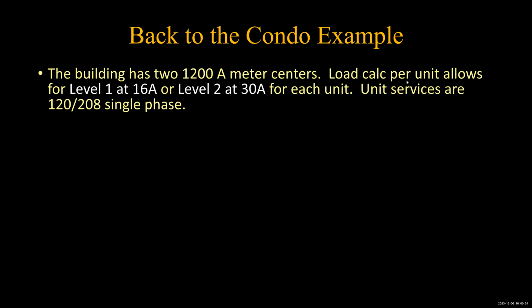You would have to show the individual units designed the way we did earlier, and then you'd apply that 23% diversity factor. I mean, that's legit, because you're including the EVs as 125% for each unit. And so you could do that, but it's probably going to bump up your individual unit service significantly. I'd love to see what the number result comes out. I'll try that sometime. So I would say try it both ways, run the calculations both ways, and then ask the owners what they would prefer.